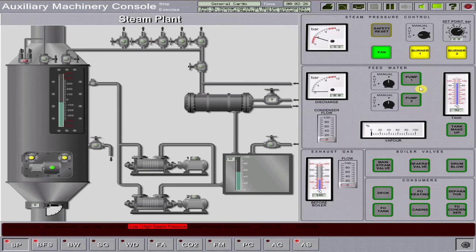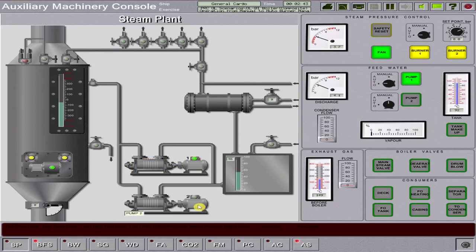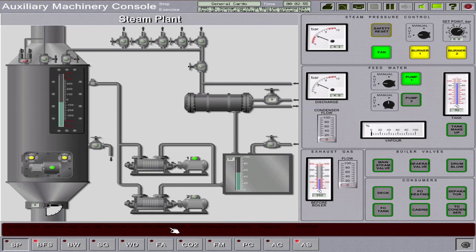Check if your feed water is running. If not, your feed water pump should be operated. Start one feed water pump and set it to automatic running. Wait for the steam pressure to rise and monitor the pressure gauge. Once there are no more alarms, you can now open the main steam stop valve of the boiler.